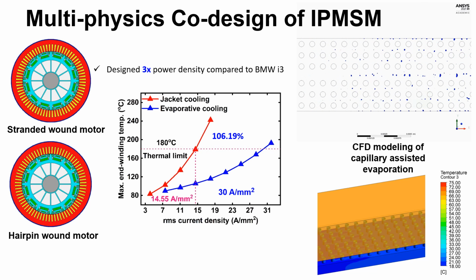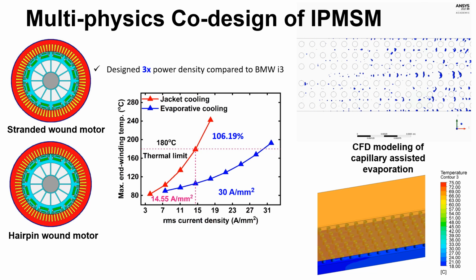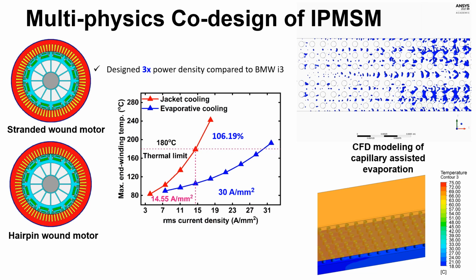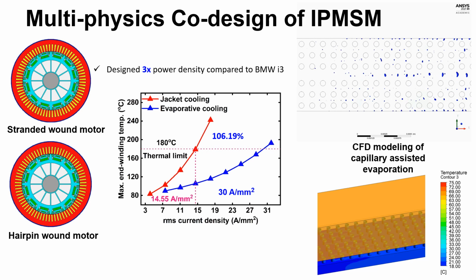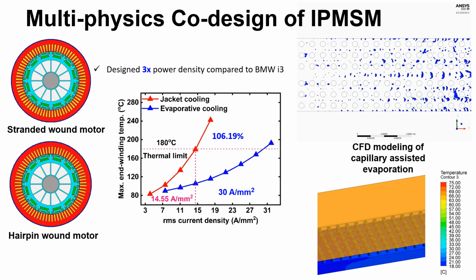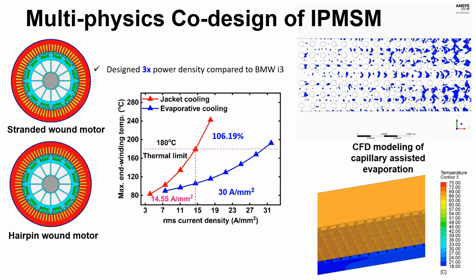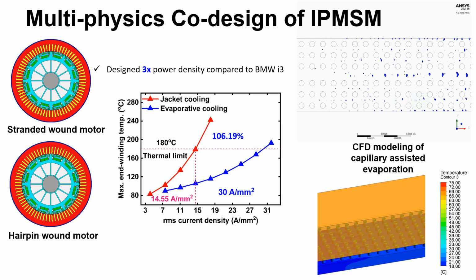Compared to the single-phase water ethylene glycol cooled jacket design, our evaporative cooling approach allows for more than doubling of the current density while maintaining the maximum winding temperatures below 180 degrees C.